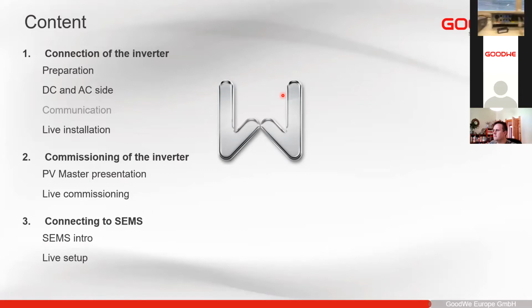So going here first, let's say the first thing you should do is maybe connect the PE cable. It's here connected on the side. Secondly, you connect the AC cable, and for this one you just have the proper cable, size it properly, and then you connect it here. You see you have the different lines here, neutral and the earthing. Now, in this case, I didn't connect it properly because we don't even have an AC output. It's just to show you how it can be done. Beneath here, you have the second connection. Maybe you see it better here.